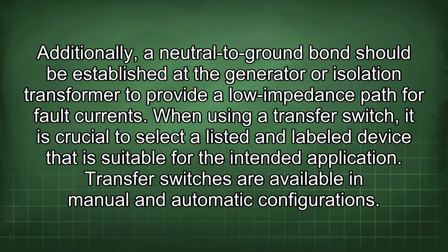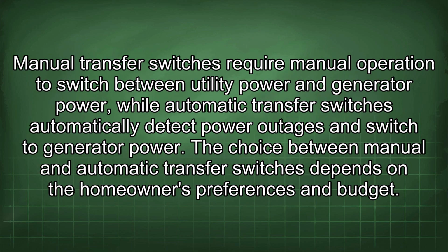Additionally, a neutral to ground bond should be established at the generator or isolation transformer to provide a low impedance path for fault current. When using a transfer switch, it is crucial to select a listed and labeled device that is suitable for the intended application. Transfer switches are available in manual and automatic configurations. Manual transfer switches require manual operation to switch between utility power and generator power, while automatic transfer switches automatically detect power outages and switch to generator power.